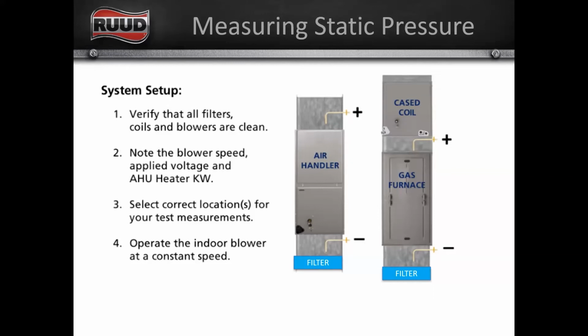So yeah, in a perfect world, right? And I get it, the world is imperfect, but in a perfect world, 0.5 or a half inch of total external static is perfect, right? Which leaves you 0.25 on the return and 0.25 on the supply. Now the blower tables, depending on what motor we're looking at, might go to 0.7, they might go to 1 inch of static, but that doesn't leave us a whole lot of room for a filter getting loaded up, or anything else happening with that system.